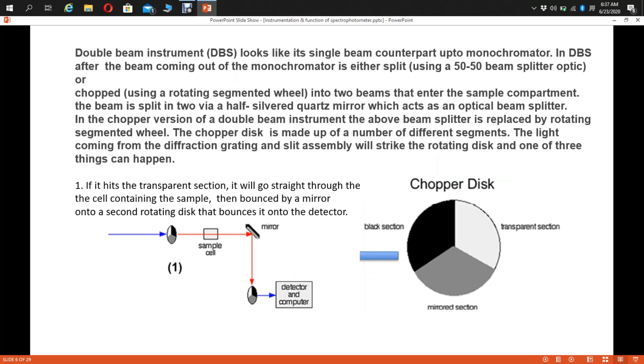Now, even with a double beam instrument, a background correction must still be performed before the measurement of any sample. This third step is used for background correction. Hopefully you will understand the function of the chopper in the double beam spectrophotometer. That makes a big difference between the single beam and the double beam spectrophotometer.